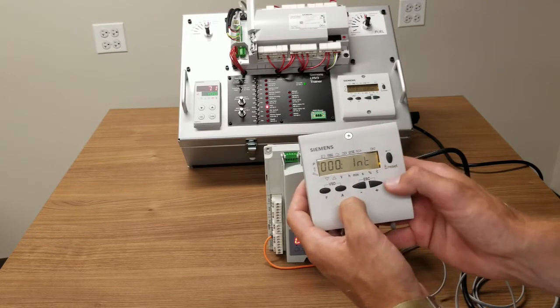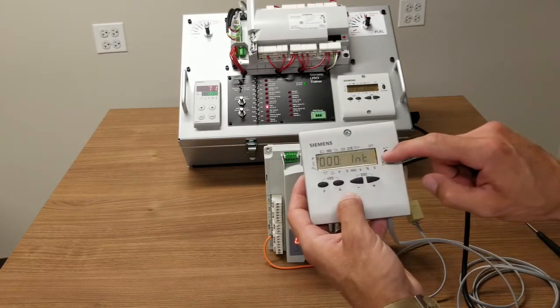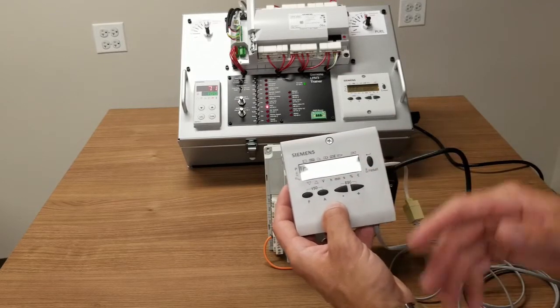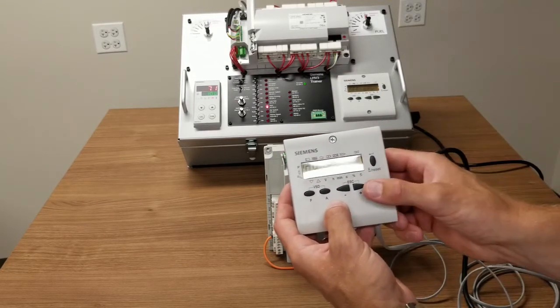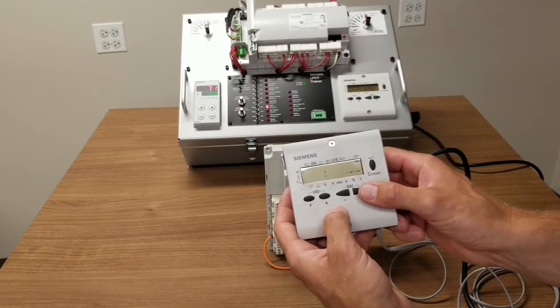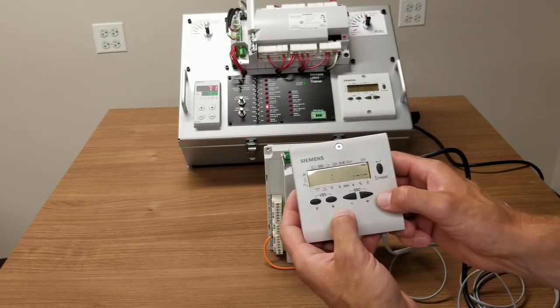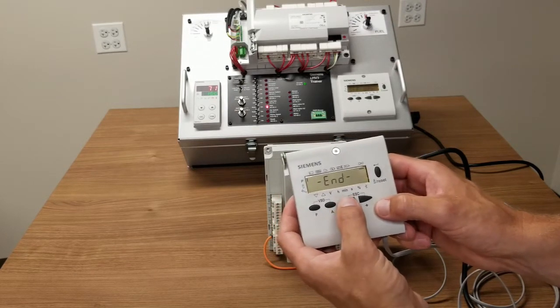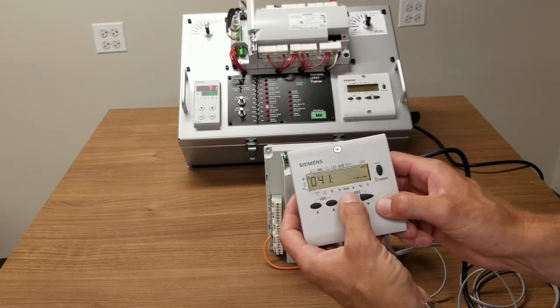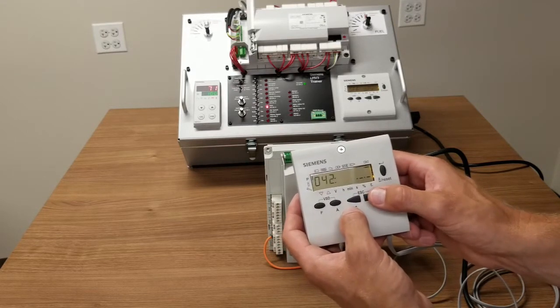To get into a submenu, simply hit the enter or reset button and it will take you into the submenu, in this case of the zero set, and that includes any parameter starting with zero, so any parameter under 100. Hitting plus or minus will allow you to simply scroll through the list of parameters in that subset.